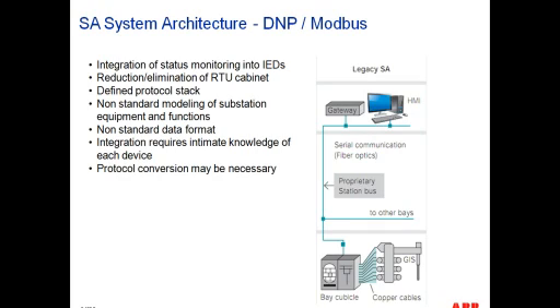So now our protection relays have communications capability, the protocols. Some of the widely used ones would be DNP, Modbus, or 103. And the idea is that your protection relays already have all the process-related information, so why don't we make that available to our substation gateway, which in turn will be able to provide a visual of the status of our substation in the form of a digital HMI. Okay, and now let's move on to our next slide.